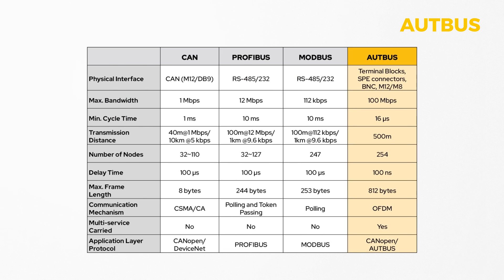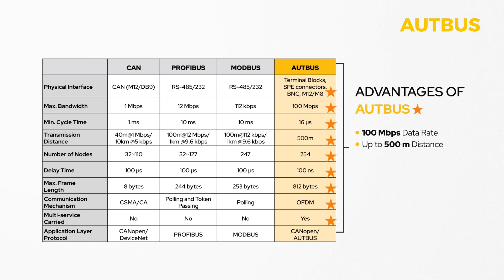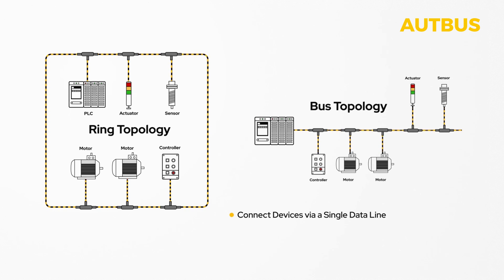AUTBUS has several advantages compared to other fieldbuses. It enables transmission speeds of 100 megabits per second, supports a maximum distance of up to 500 meters, accommodates up to 254 multi-drop nodes, features a 100 nanosecond delay time, is adjustable for data frame length, has a cycle time of 16 microseconds, and allows for the prioritization of data. The multi-drop connection of devices via bus or ring topology makes it possible to connect several devices via a single data line.